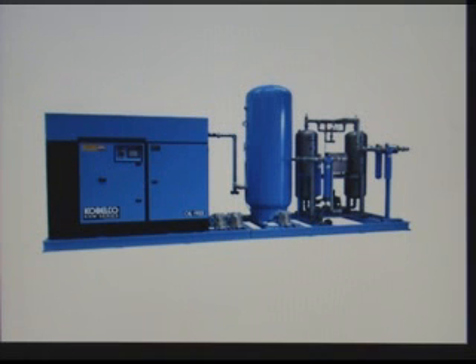Now this first bed will need to be regenerated so that it can be brought online when the second bed gets saturated. And that's done by a bypass, which bypasses dry air through the desiccant bed and purges all of the water out of it into a drain system. So in this way, by swapping back and forth between these two desiccant towers, you can continually supply whatever dew point air you have at whatever flow rate you need, just by varying the size of the compressor, the receiver, and the air dryers that you have.